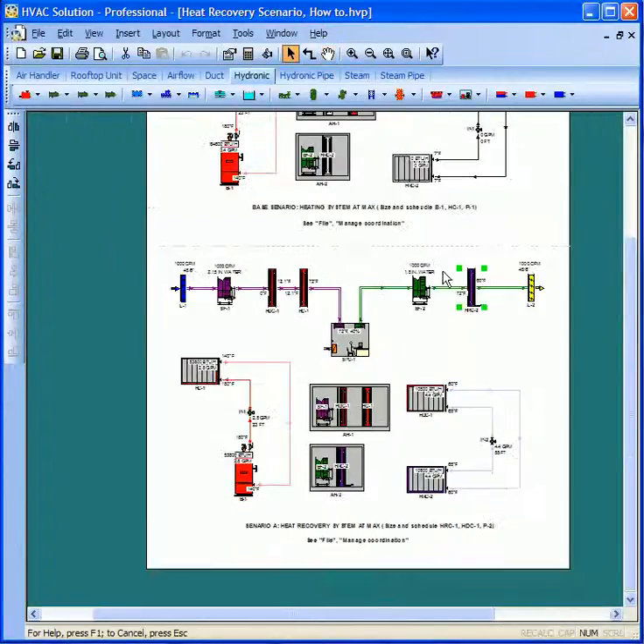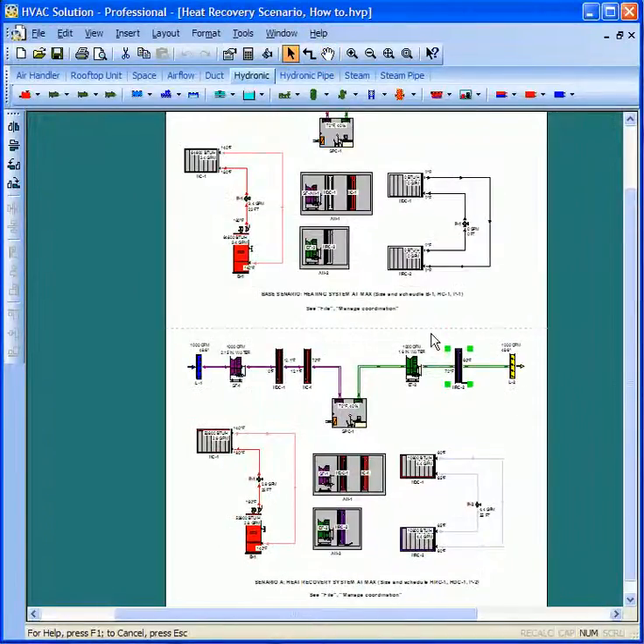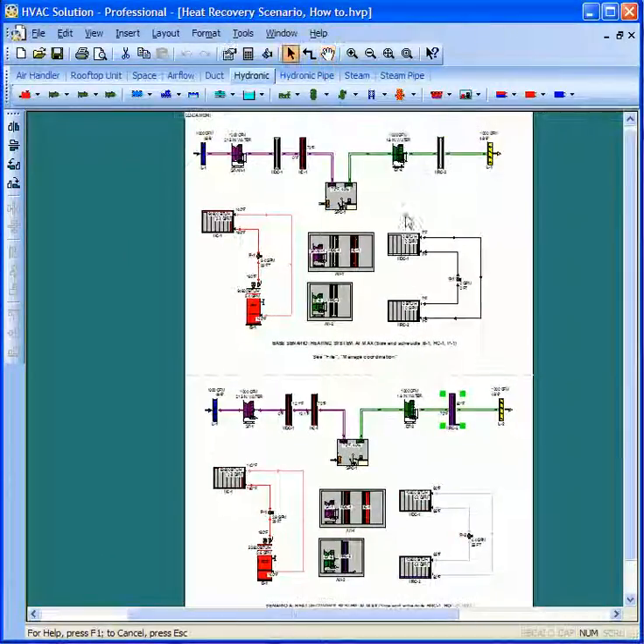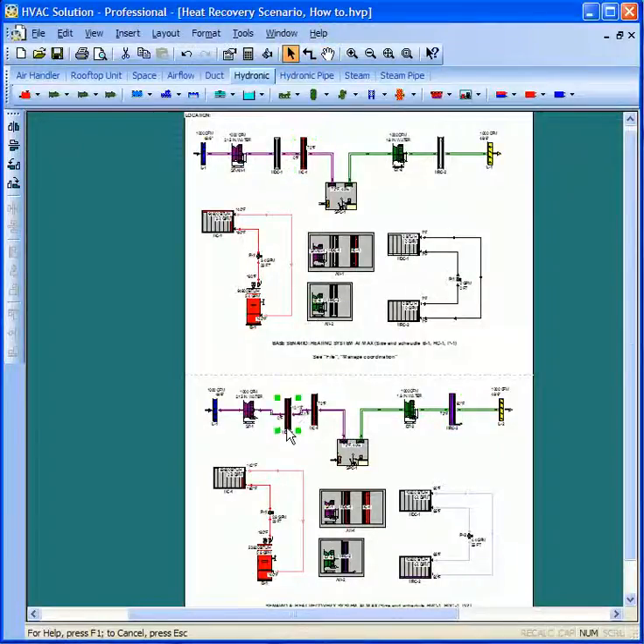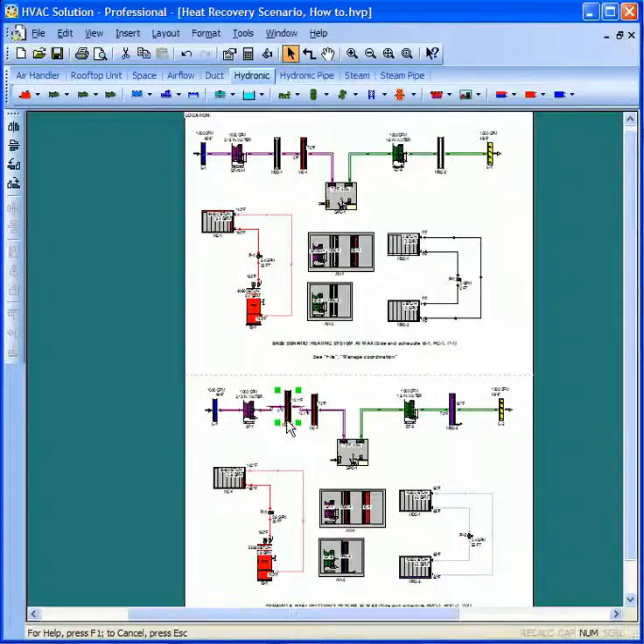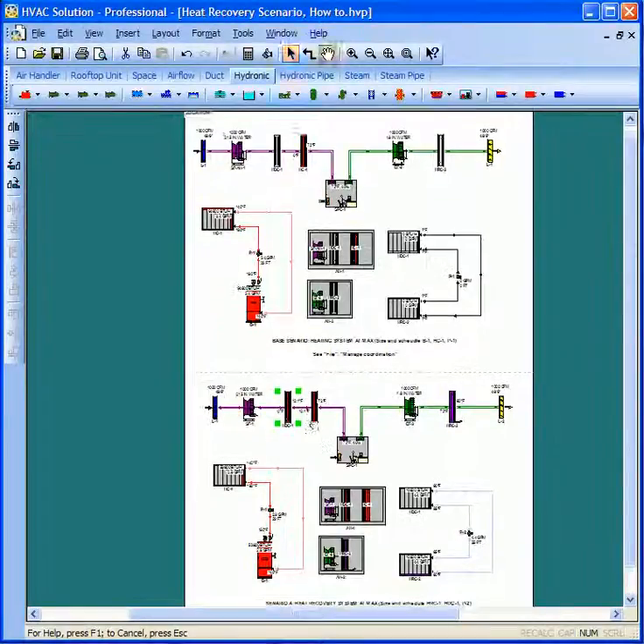In order for me to schedule both of these, the best of both worlds, I want to size this heating coil in the top scenario for maximum, but then I want to size this heat recovery delivery coil for maximum in the bottom one.